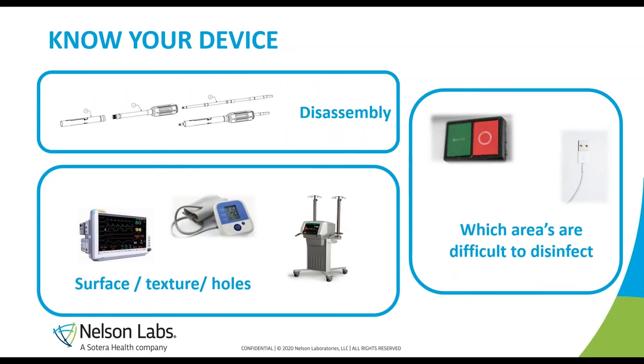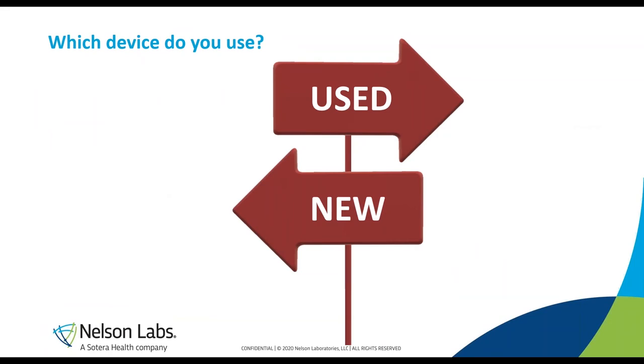Also know your device's details: can you disassemble it? What are the surfaces like — are there holes or difficult textures? Which areas are touched most, like an on/off button or plug? Know how the device can be disinfected and where the areas are that are difficult to reach, where microorganisms may be present but hard to access, or where the device is touched the most.